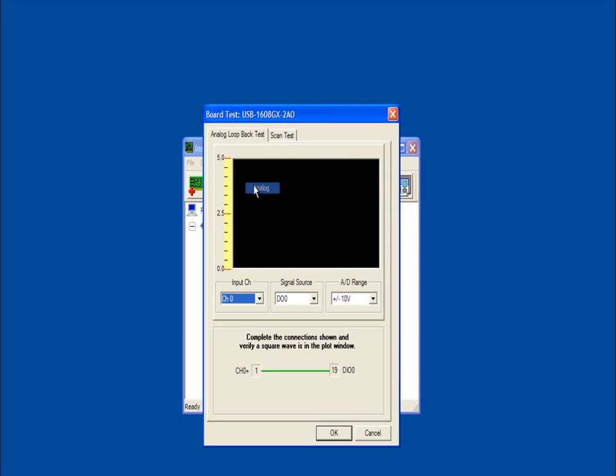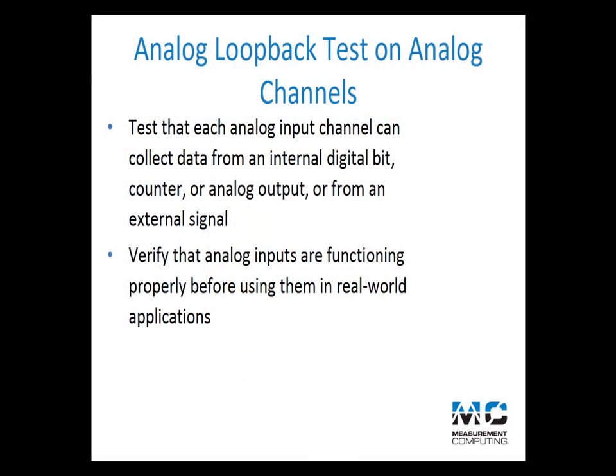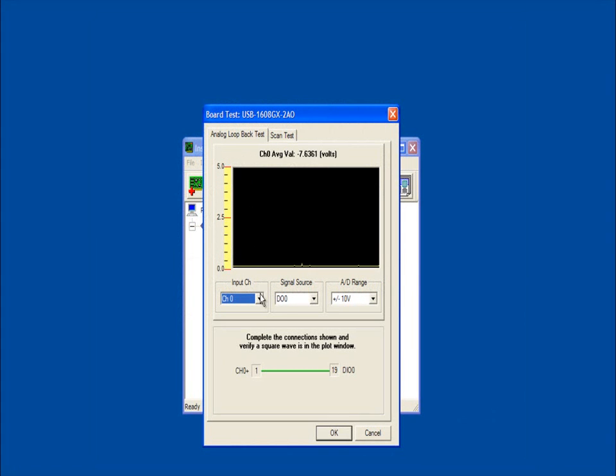To test each analog channel on your device, select Test Analog from the Instacal menu bar. The analog loopback test takes an internal digital bit, counter, or analog output from your device and loops it back to an analog input for viewing on the display panel. You can also perform this test using an external signal. This simple test verifies that the analog inputs are functioning properly. On the Board Test dialog box, select a channel and associated A to D range to test, and select the signal source to use. The available signal sources vary depending on the device features.